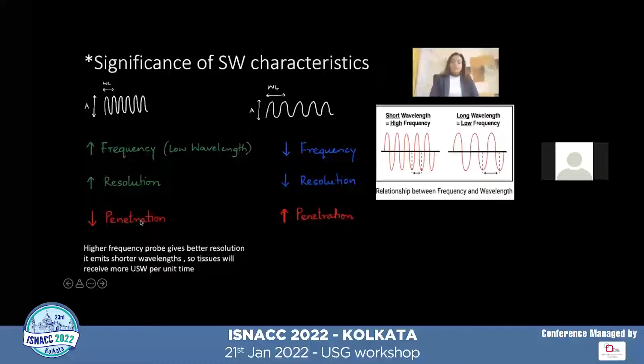Because the tissues will receive shorter wavelengths, that means they will receive more ultrasound waves per unit time. The drawback of higher frequency is that it has high attenuation, causing a decrease in the penetration. So higher frequency probes have better resolution, but they are useful for viewing superficial structures only, not the deeper ones.